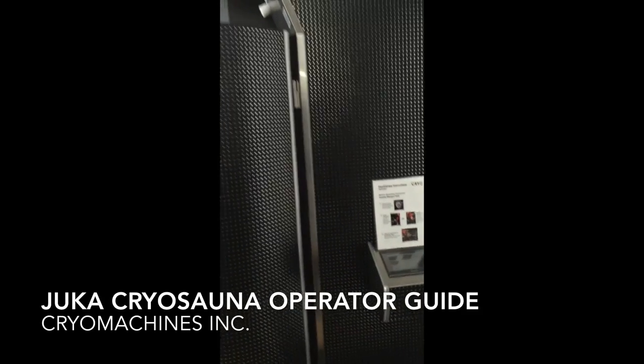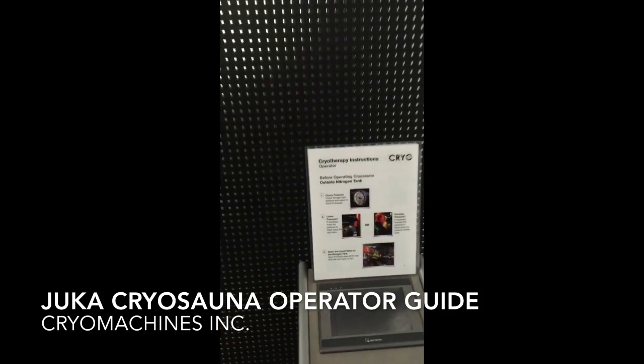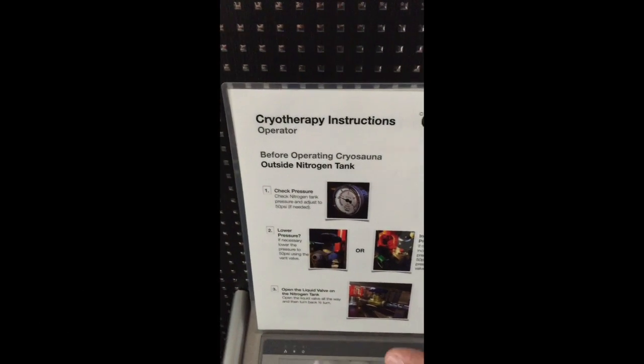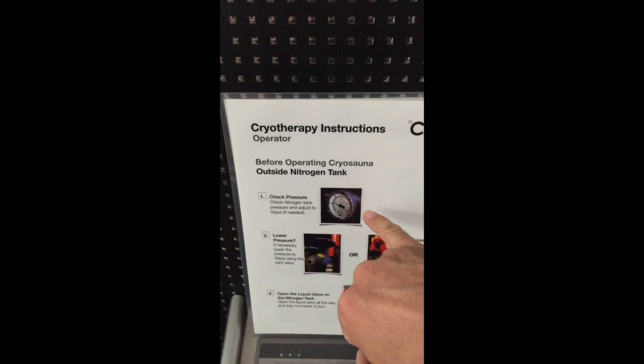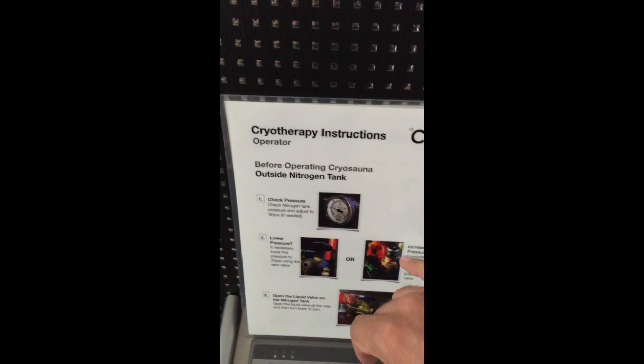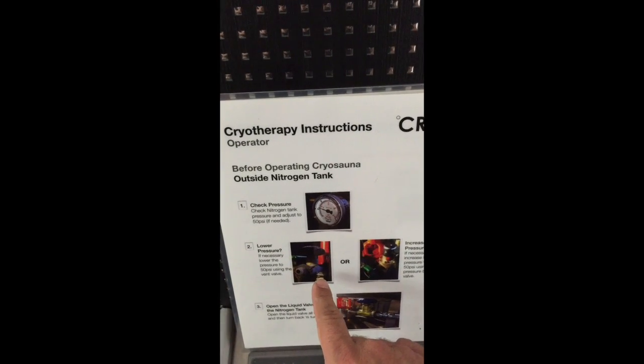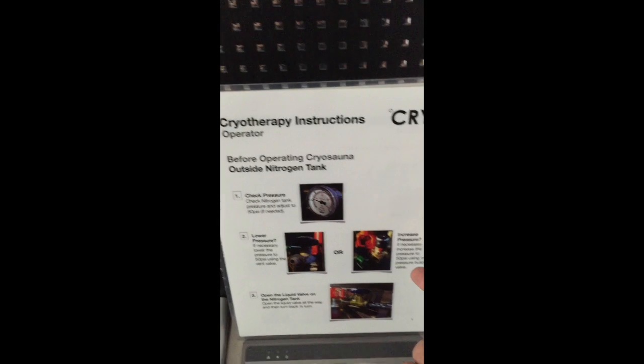To operate a JUKA cryo sauna, start by opening a nitrogen tank. Check the handout the technician gave you — it walks you through the checkpoints. Check the pressure first; it should be around 50 psi unless instructed otherwise. You can lower the pressure with the vent valve or increase it with the pressure builder.